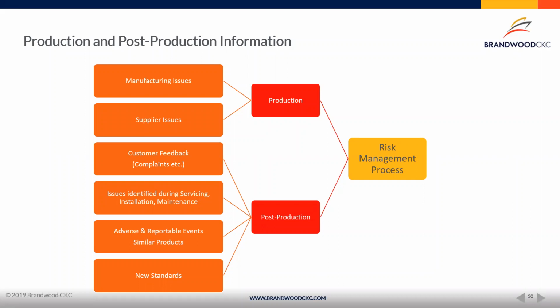So let's just take an example. If you had an implantable orthopedic product, let's say it's brand new and slightly different, you may be able to identify some risks from other people in the space. So the hip implants, or for anybody doing a knee implant, you might be able to take some of that information and identify those risks that were specific to those products, but apply it to your product appropriately. And again, there's two things that come out of that. One is identification of new risks, so risks that you wouldn't have identified previously. And the second is whether or not the severity or probability of this happening is appropriate for the way you've addressed it initially.